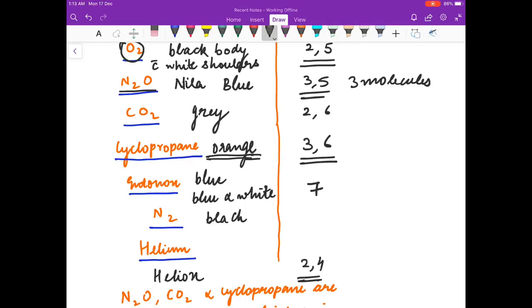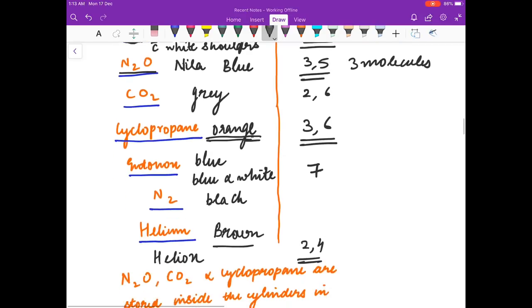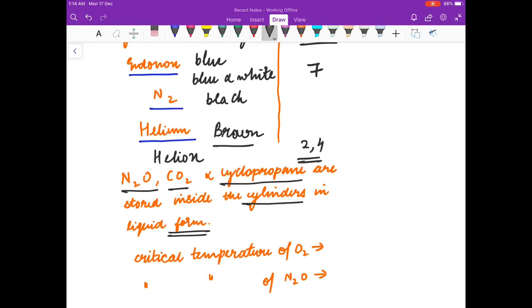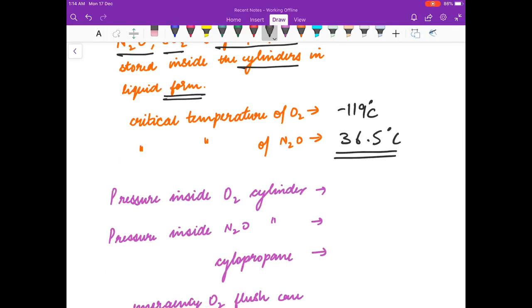Friends, hope you will learn this by heart. Remember that nitrous oxide, carbon dioxide, and cyclopropane are stored inside cylinders in liquid form. The critical temperature of oxygen is minus 119 degrees Celsius. For nitrous oxide it is 36.5 degrees Celsius. The pressure inside an oxygen cylinder is 2000 psig.